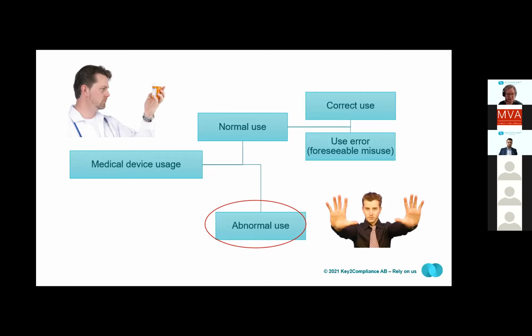You may, of course, be in situations where healthcare personnel, where healthcare institutes decide to, on purpose, go on and use the device in a different way. And that is something in the end that you cannot, as a manufacturer, take responsibility for, and to some extent you can never influence. You may not hear about it, but when you hear about it, you are obliged to stick to your message, stick to your approved intended use, and communicate that what you're doing now is on your own risk and it's not part of our approved intended use.